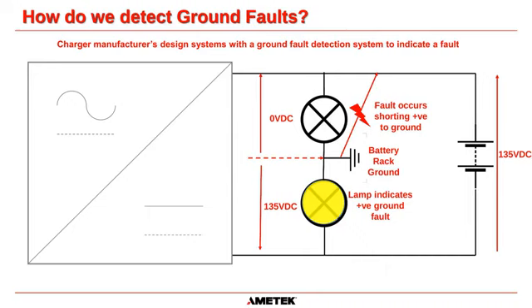Okay, so why use 2 lamps? Very easy, because if you have a direct short between positive and ground, let's say the insulation on this positive wire has failed and is touching the cable tray, which is grounded, then now we have a direct connection between positive and ground. Well, now you're going to have 0 volts DC across this lamp, and that lamp is not going to light anymore. It needs potential to light. But if you go between negative and ground, because this point here is now at 135 volts potential, this lamp is going to go very bright. And that's what indicates that you have a positive ground fault on the system. Okay? Hopefully that makes sense.